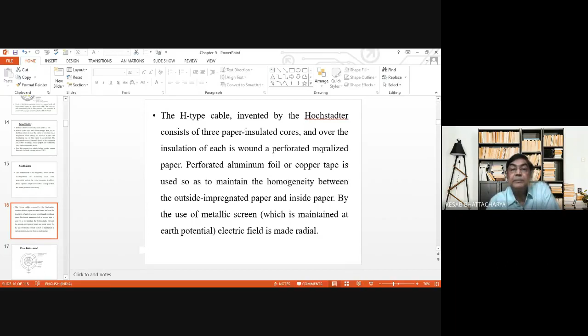A perforated aluminum foil or copper tape is used to maintain the homogeneity between the outside impregnated paper and inside paper. By the use of a metallic screen, which is maintained at earth potential, the electric field is made radial.